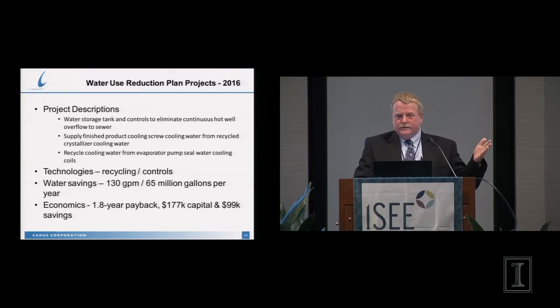The way the crystallizer cooling water loop works is that water provides seal water to the barometric condenser. It also cools steam vapor coming out of the crystallizer, which creates a lot of vacuum. If we lose water flow to the barometric condenser, that's a catastrophic event, because if you lose the vacuum, everything that's in that 100-foot tall tower just drains right out of the bottom.